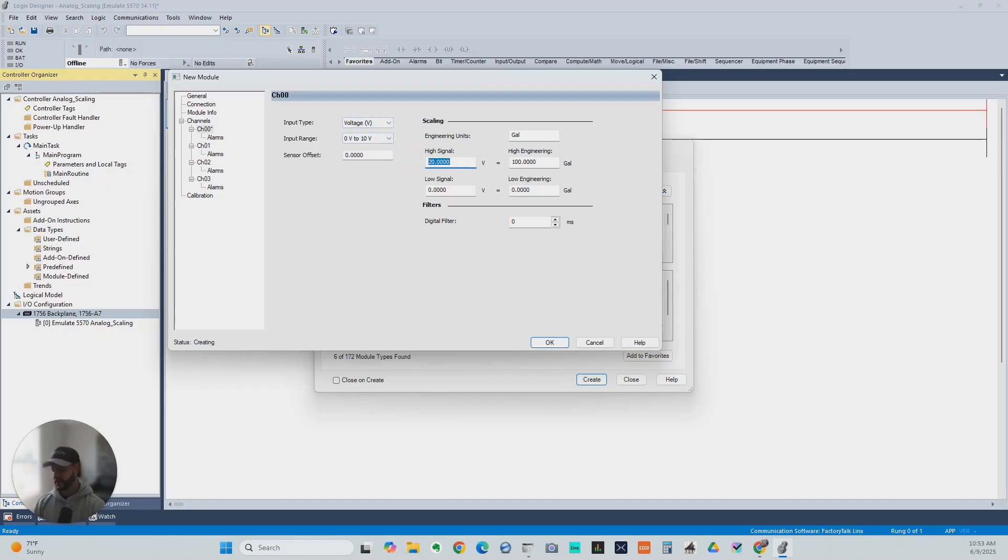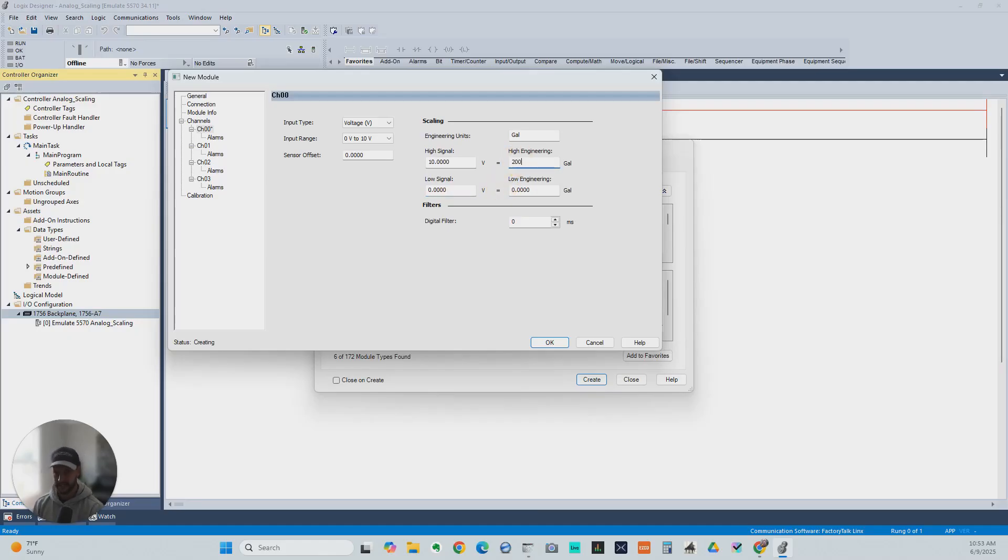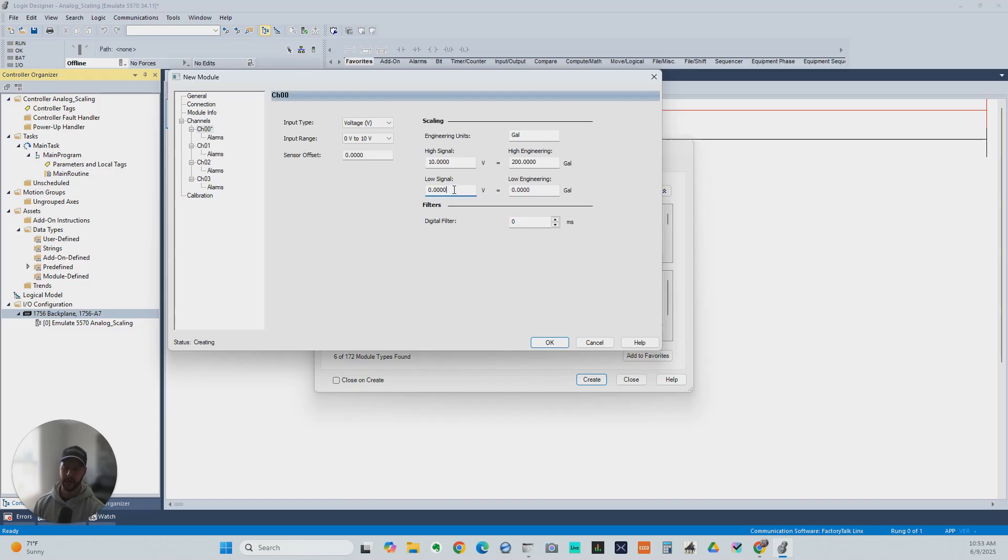Our high signal we're going to say is 10 volts, and our low is 0. We said this is a 200-gallon tank, so now we set that to 200. So now, if we see 0 on our analog input signal, that's going to be 0 gallons in the tank.